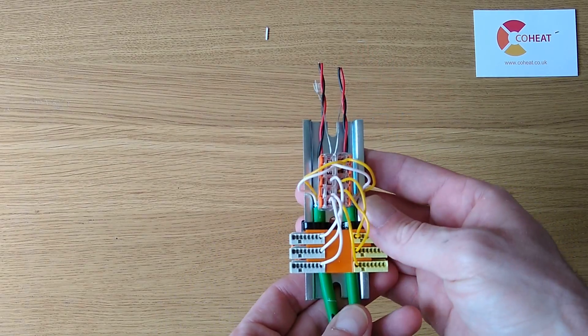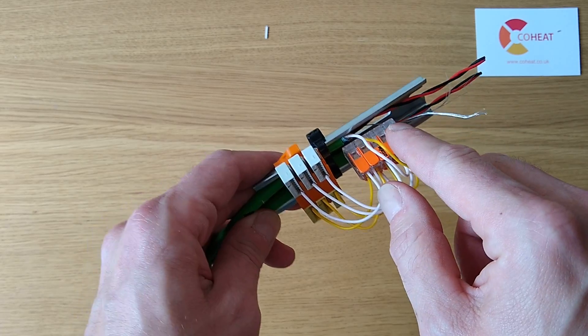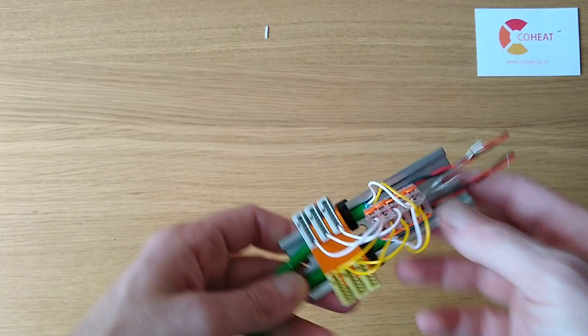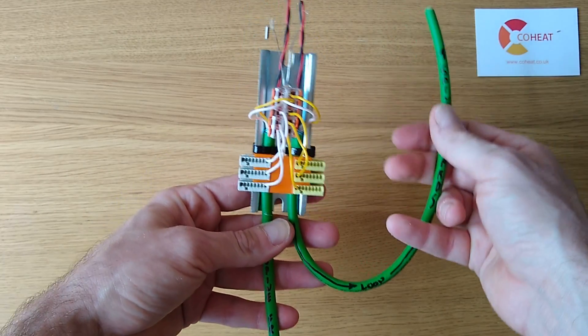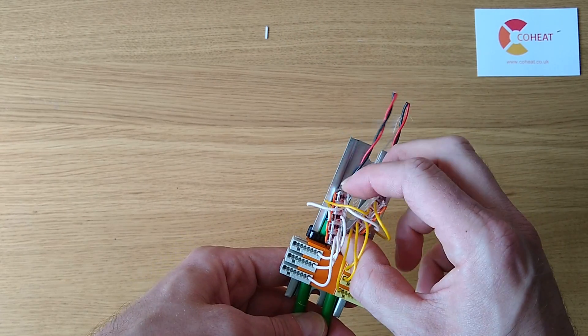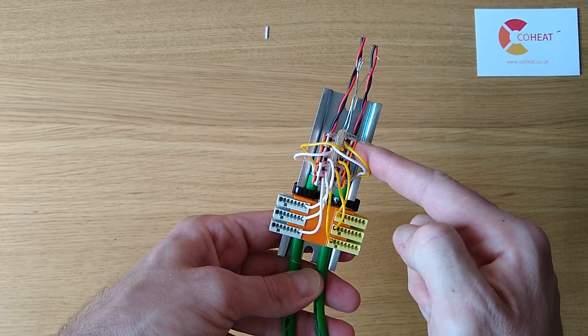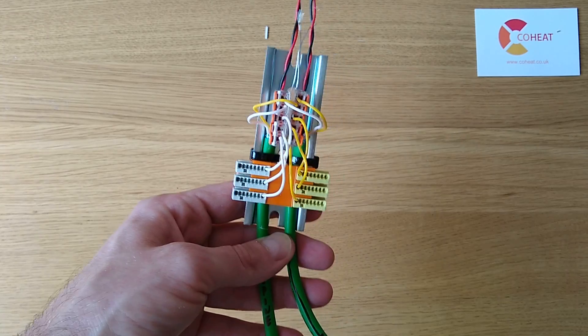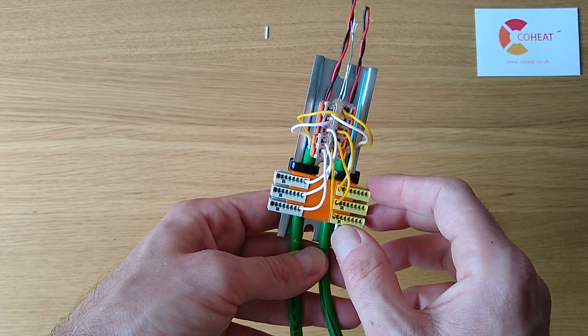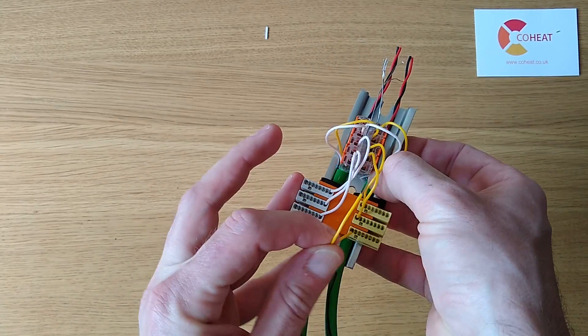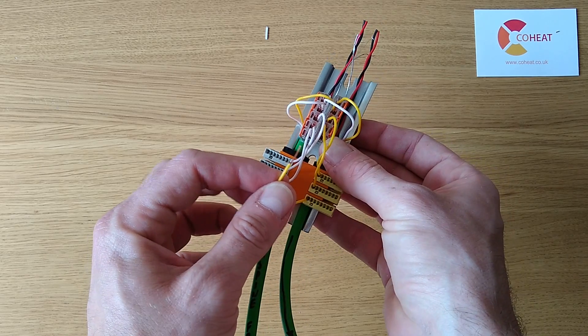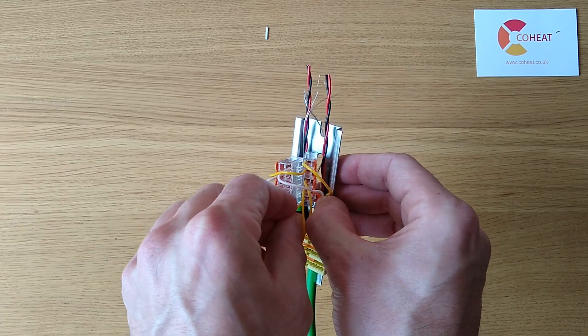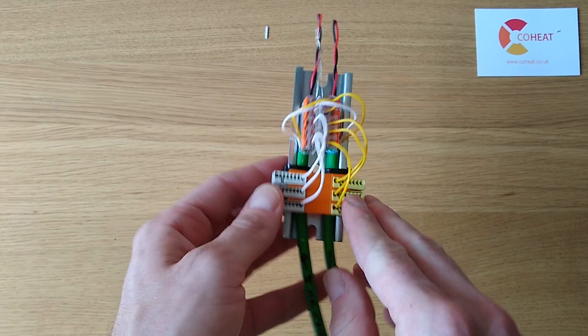Another way of doing this might be to use Wagos for the spine, and then these KNX connectors for the HIUs. So here we'd have the spine coming up from the bottom and up to the rest of the site. And we've taken it into a pair of Wago blocks. From these Wago blocks, we've gone to three sets of KNX connectors, and we can run our HIUs out from these. The advantage of doing it this way is it's quicker to flip a Wago spring and disconnect an entire set of HIUs for fault-finding purposes.